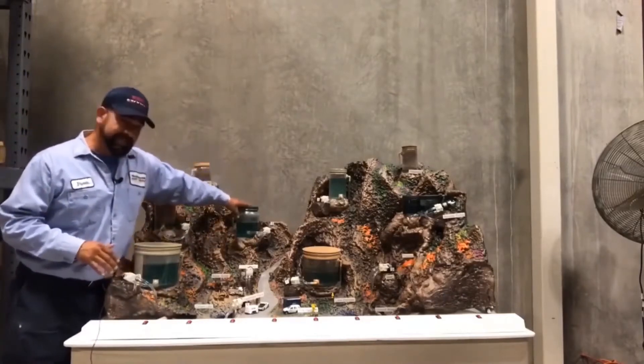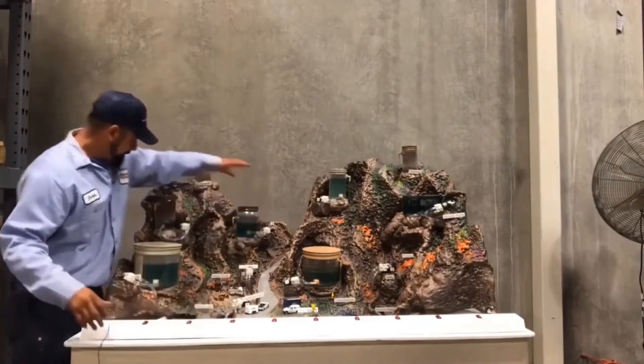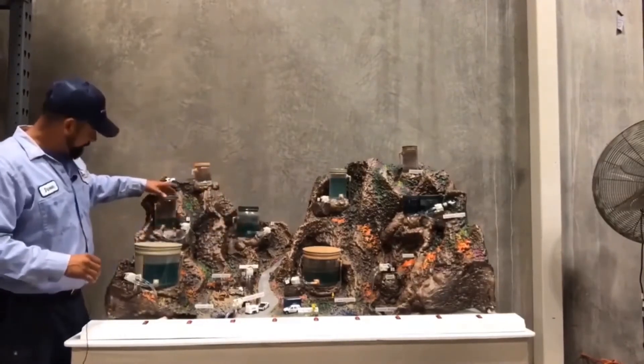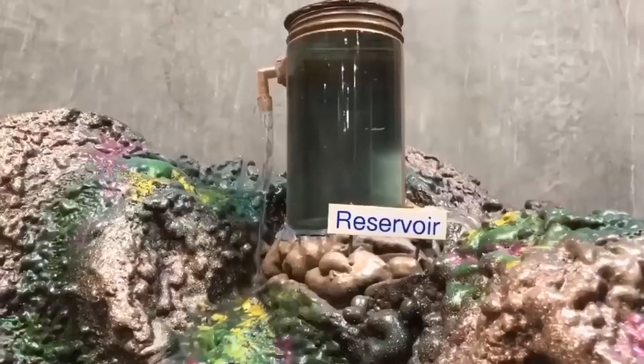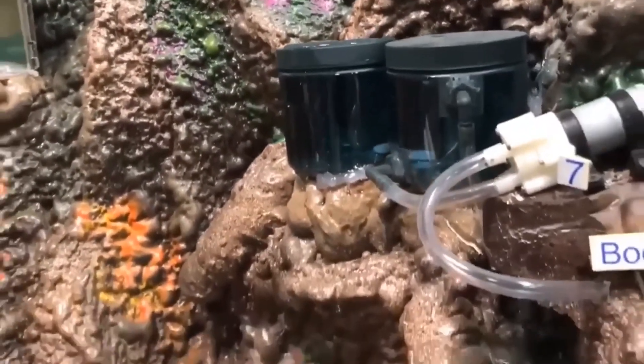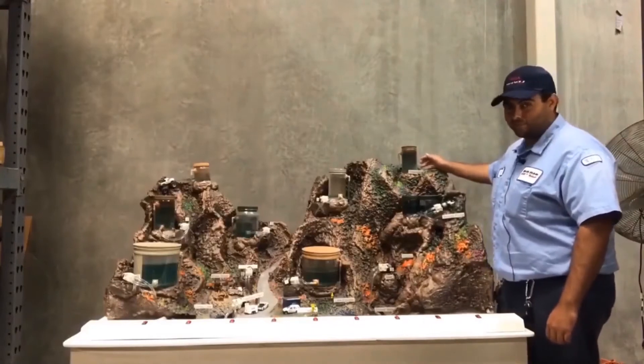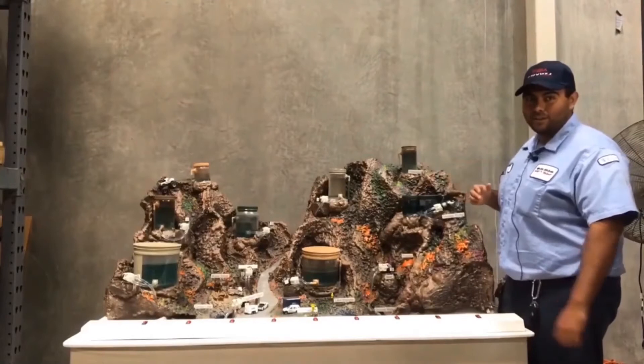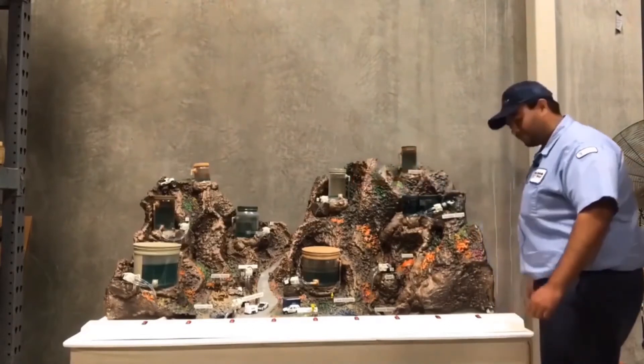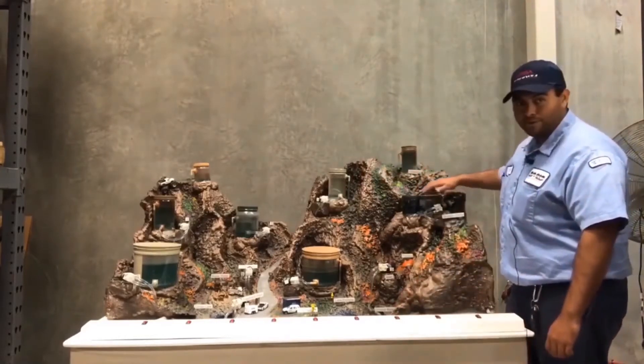For example, this tank here is about halfway full. If we turn on that booster, it's going to push water to this tank, which is a little bit higher. As you can see, it's spilling. If I continue to overflow the tank, that booster is pulling from a different tank — and if I'm not taking care of the levels on the other tank, I can either overflow the one it's pumping up to, or drain the one it's pulling from. To stop that from happening, you have to monitor all the other tanks and make sure they have adequate water to move it all the way up.